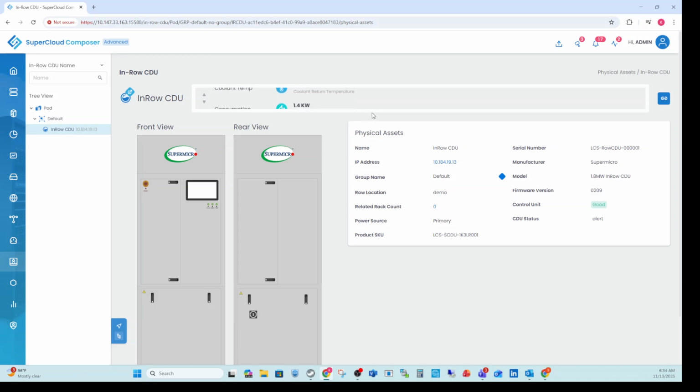And in the top here, we provide you with a carousel view, a high level view of sensor data collection that we are exposing within our platform to provide your essential lifecycle management for a liquid cooled data center. You'll notice that when the mouse is placed into the carousel view, the data stops scrolling.